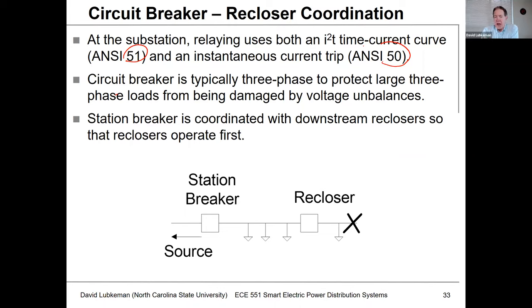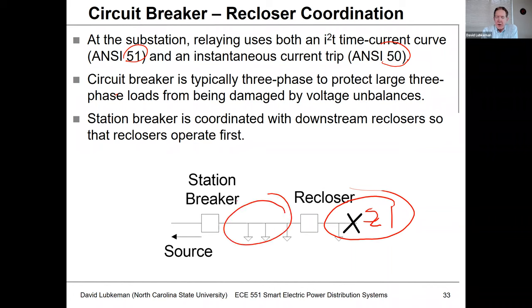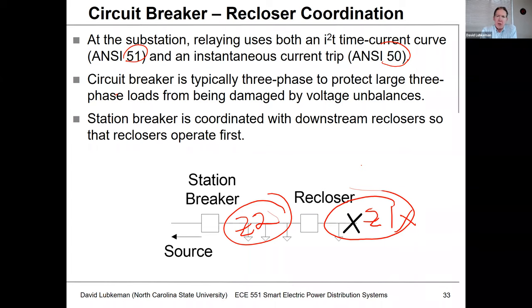As far as coordinating with downstream reclosers, we want the recloser to handle any faults below that device. In this simple example, the recloser protects zone one and the breaker protects zone two. Anytime there's a fault in zone one, we want the recloser to operate first so upstream customers are not outaged. For a fault in zone two, the breaker operates, and the breaker also serves as backup for the recloser if the recloser fails to clear a zone one fault.